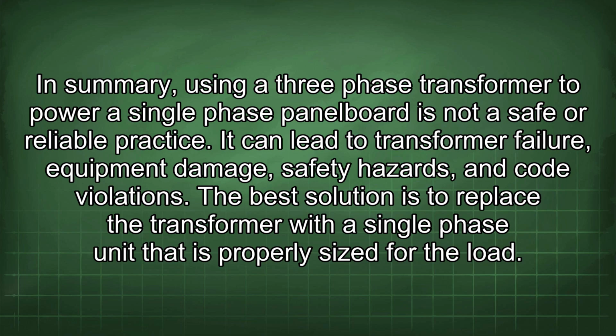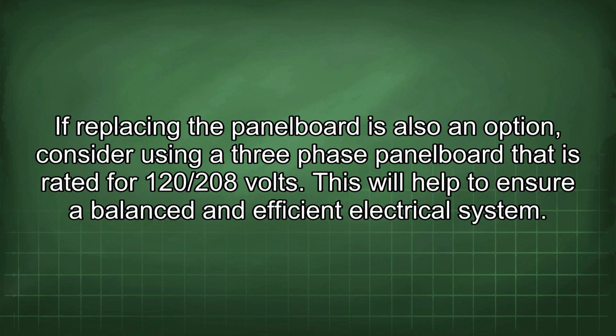In summary, using a 3-phase transformer to power a single-phase panel board is not a safe or reliable practice. It can lead to transformer failure, equipment damage, safety hazards, and code violations. The best solution is to replace the transformer with a single-phase unit that is properly sized for the load. If replacing the panel board is also an option, consider using a 3-phase panel board that is rated for 120/208 volts.